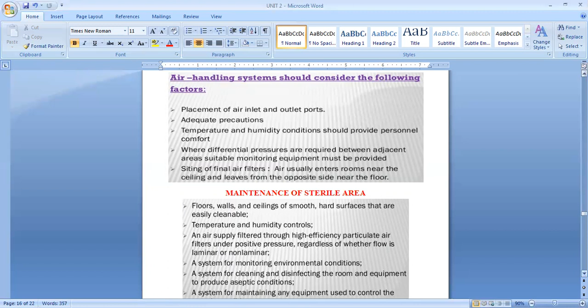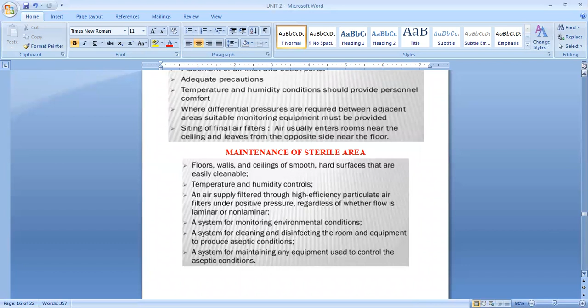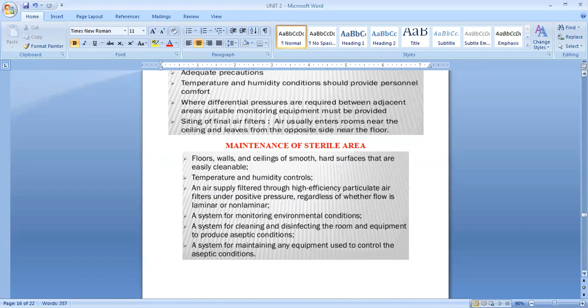Maintenance of sterile areas: floors, walls, and ceilings of smooth, hard surfaces that are easily cleanable. Temperature and humidity control and air supply filtered through high-efficiency particulate air filters under positive pressure, regardless of whether flow is laminar or non-laminar. A system for monitoring environmental conditions. A system for cleaning and disinfecting the room and equipment to provide aseptic conditions.